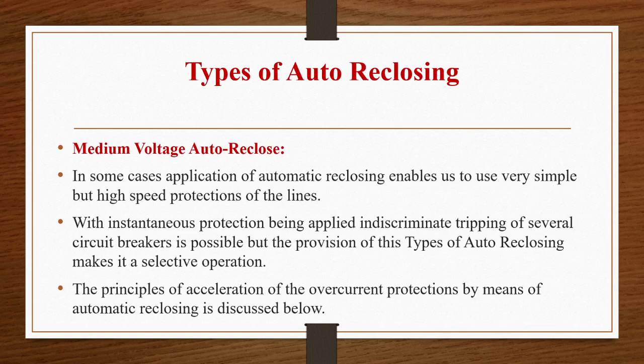In some cases, application of automatic reclosing enables us to use very simple but high speed protections of the lines. With instantaneous protection being applied, indiscriminate tripping of several circuit breakers is possible, but the provision of this type of auto reclosing makes it a selective operation.